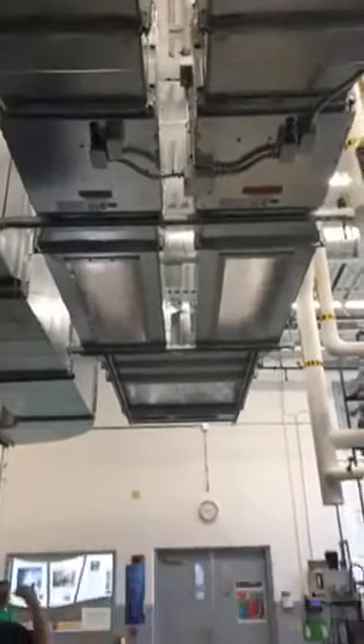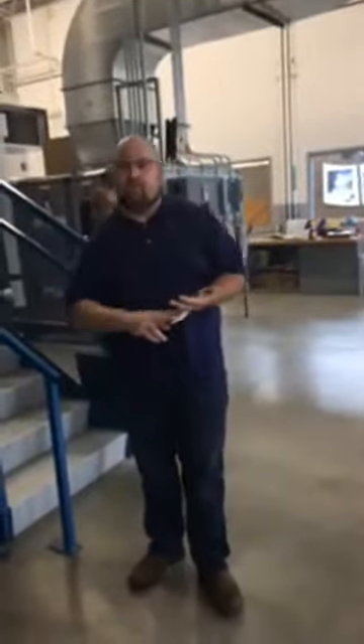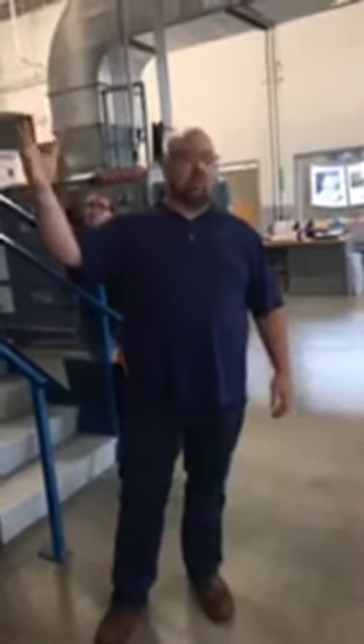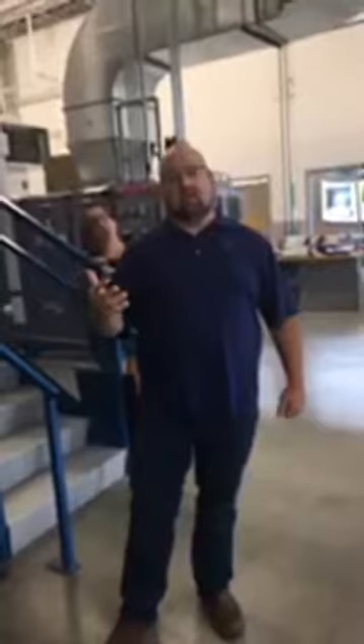So right now, within the building, these being fire smoke dampers, if this was an actual fire existing in the ductwork, there is a temperature sensing device on a fire smoke damper that would activate to slam it shut. Most buildings today with a fire smoke damper, it's also tied in with a smoke detection system. So in this case right now, I'm going to show what would happen if we had a fire in the building, the ductwork is filling with smoke, a duct-mounted smoke detector head has picked that up and is going to put it into an alarm.